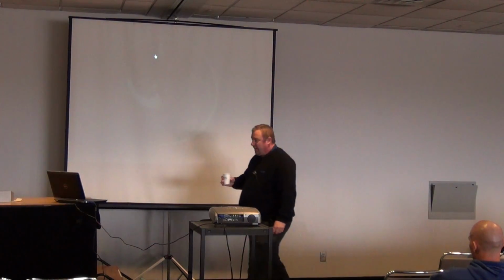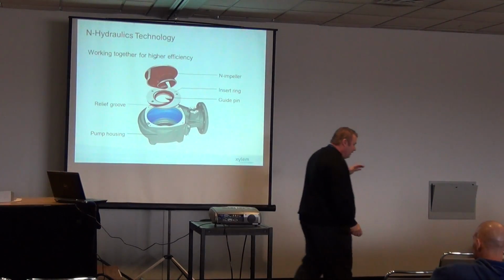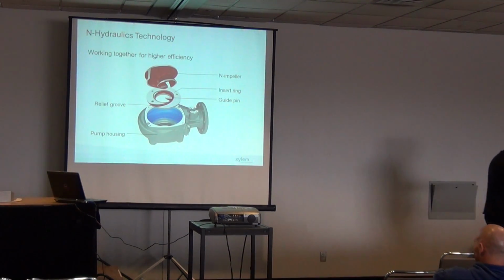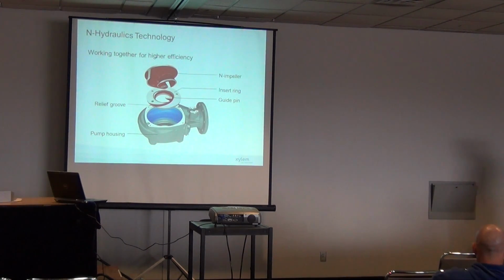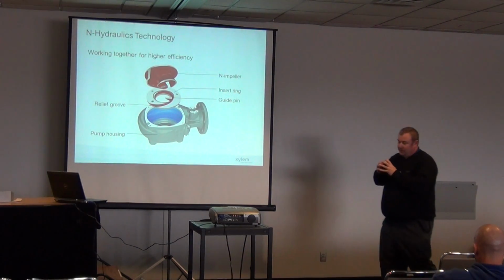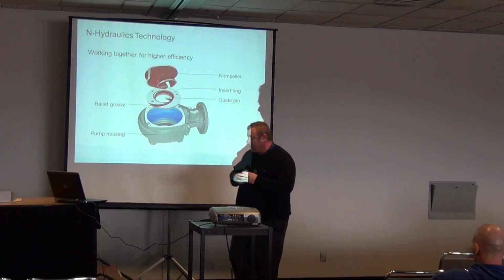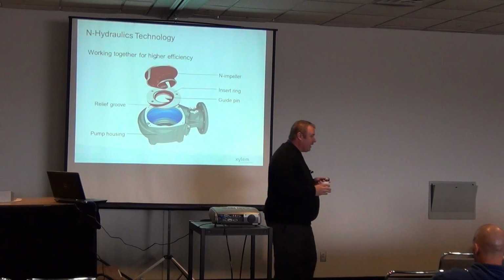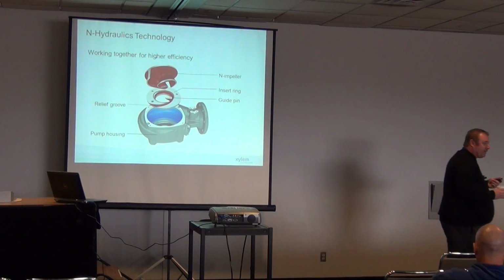So what does that really mean? When you couple this with the controller, it actually means that we can pass those materials through the pump, we can sustain efficiency over time, and when you look at standard channel impellers, which Flygt developed for a long, long time, and many of the competitors out there do, there was a soft clogging phenomenon, meaning that the stringy materials, some of these rags in the system, the wet tex items that we're seeing in the wastewater stream, would ball up on each other and give partial clogs in the pump itself. So you might still be pumping, and burning electricity the same amount, but you're not getting as much flow.